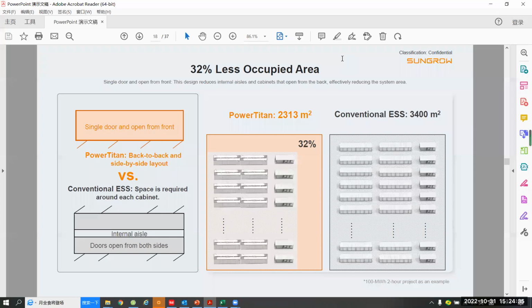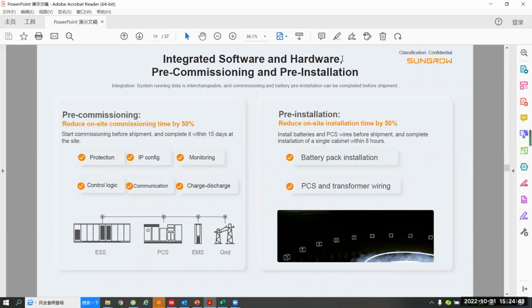Also, Sungrow as a professional BESS integrator, all the BMS, PCS, and EMS are self-developed by Sungrow ourselves. We can do the pre-commissioning work and pre-installation work. On pre-commissioning work, we can do the protection test, control logic test, communication test, charging and discharging of ESS test, and the monitoring test at the Sungrow factory. This can reduce the commissioning time on site by 50%.